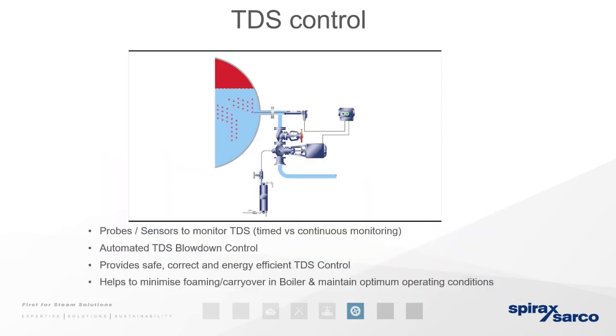The TDS control. So again, we should be monitoring the TDS, the total dissolved solids. We can do that in various different ways. You can use probes, sensors to monitor the TDS. So we can release it timed. So you can say that it's set for every 2 hours, 3 hours, or continuous monitoring. So you have a set point where you are deciding to blow down when it reaches that set point. All these values will be found on the plate for your boiler.